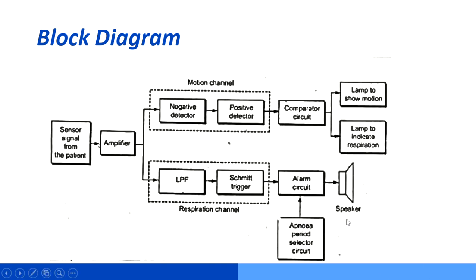The next thing is the alarm circuit. This circuit is driven by the apnea period circuit, which contains oscillators and amplifiers, and if the patient is not taking a breath for 10 seconds or 20 seconds, the alarm rings immediately, as a speaker is connected to it.